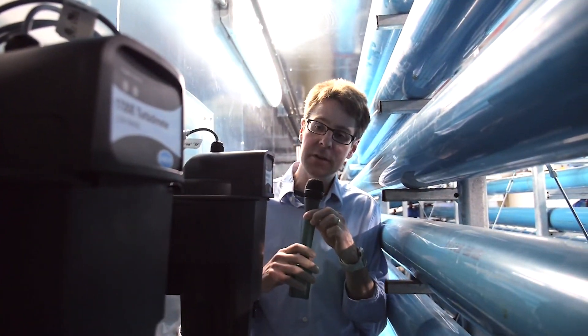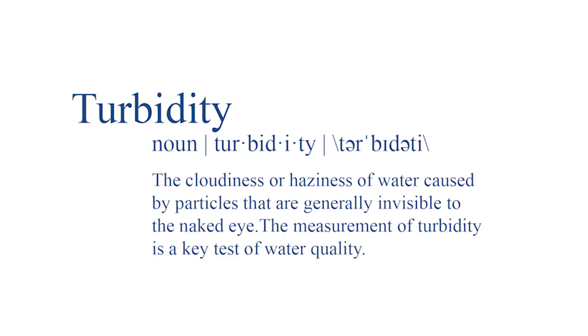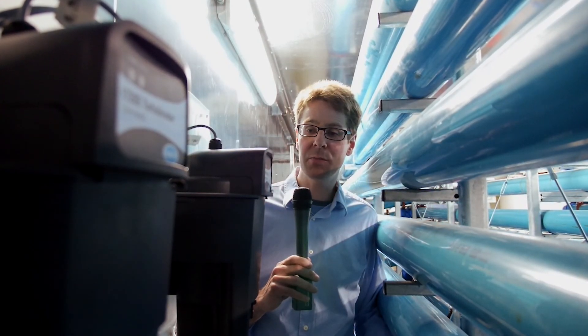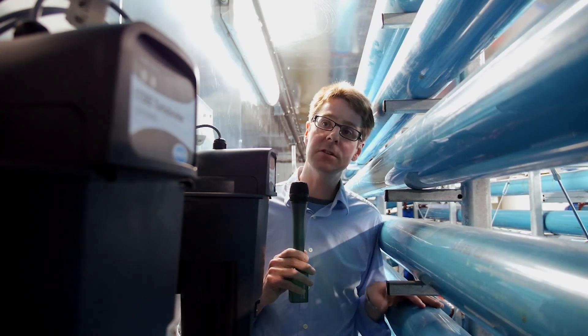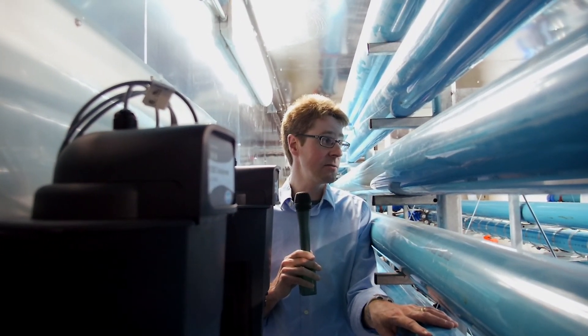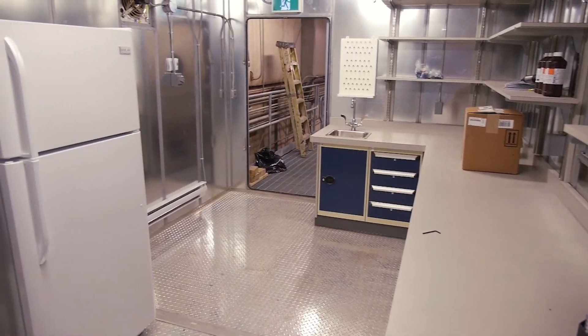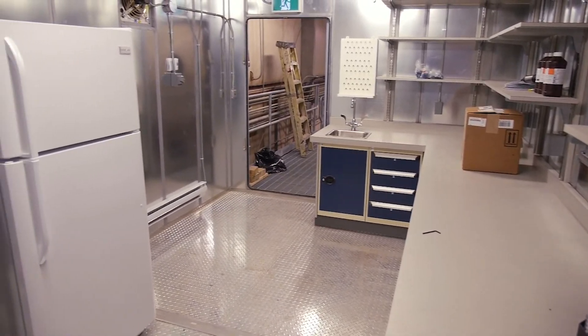You mentioned some ideas for experiments to determine the effectiveness of flushing out pipes for maintenance purposes. Water utilities in North America usually flush their systems either reactively — when they get customer complaints about red or discolored water — or proactively on a fixed schedule. Our belief is that in both cases, utilities may be using more water than actually needed to flush pipe. The materials on pipe walls are probably not as adhesive as utilities think, and much lower flows could be used. The application of this research is to find what flows are optimal for flushing PVC and lined pipe, with an opportunity to save both water and energy for utilities.